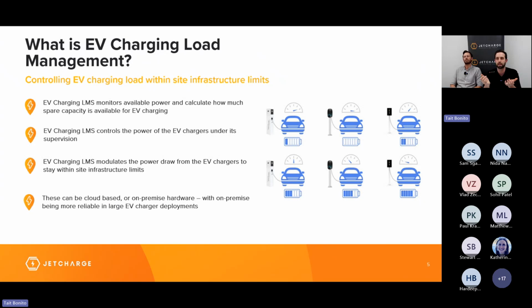This means that if EV chargers are left to operate uncontrolled at a site, that causes additional risk of tripping electrical infrastructure. EV charging load management systems monitor the spare electrical capacity at a site and calculate how much power is safe to allocate to EV charging. They then instruct the chargers to derate their power draw when the system calculates the site is approaching its electrical limits. This is how they ensure safety on site.